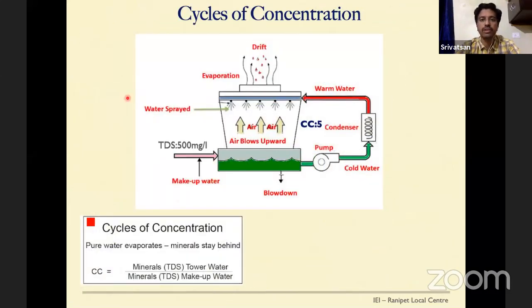Next, I would like to brief on the cycles of concentration. In the cooling water system, water from the clarified water storage tank goes into the cooling water cycle. Here, it is pumped into the condenser cycle where it absorbs the heat and the water gets warm. Then it is sprayed in the cooling tower, which is usually a natural draft or forced draft cooling tower. Here, water evaporates and there are some drift losses. And water again falls back to the cooling water channel or cooling water basin. So water goes and comes around.